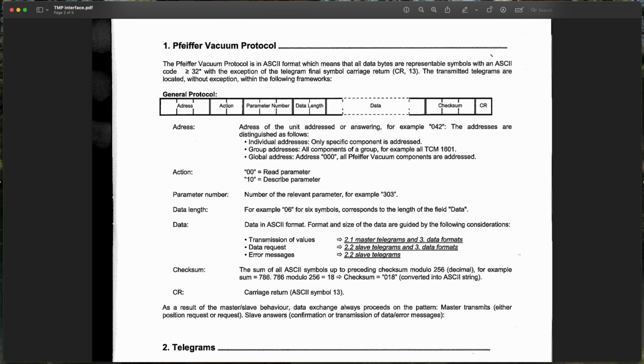As for what data actually gets sent across the bus, we need to look at this protocol document. The messages are ASCII again, which is good, but they need a particular structure. It starts with an address, so each device on the bus can tell who the message is for, then an action, whether we're reading or writing a parameter, the parameter number, some associated data, a checksum for the whole message, and a terminating carriage return. Fair enough. Should be a simple matter of programming.